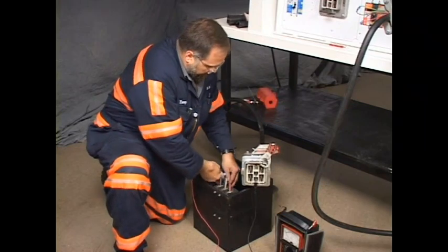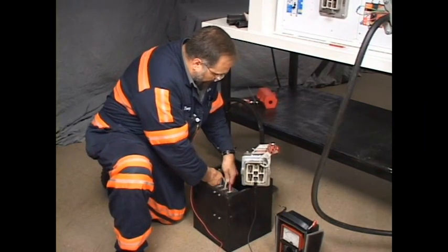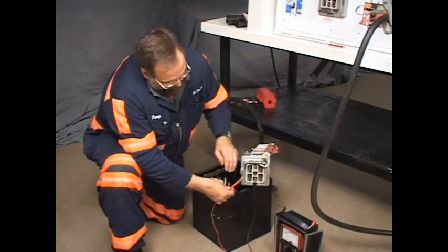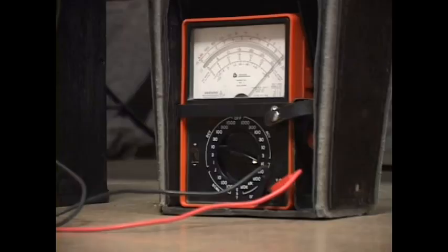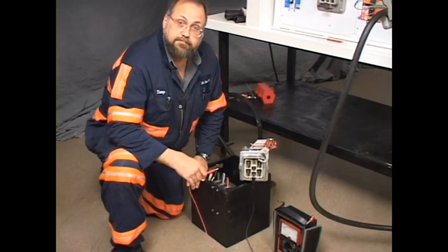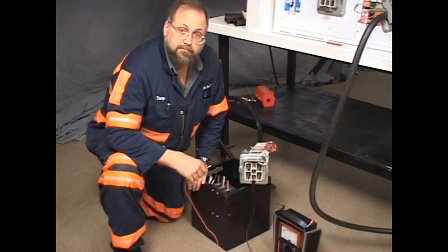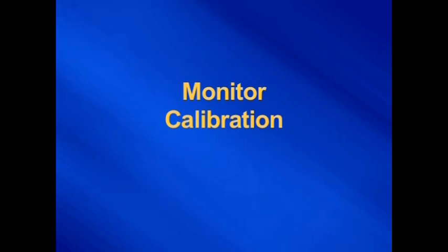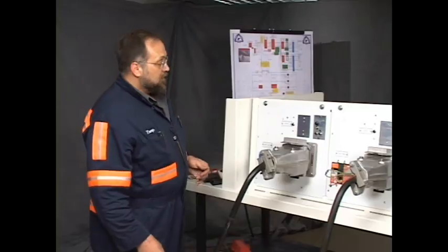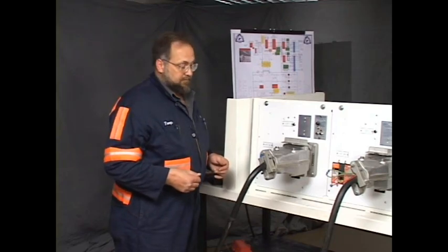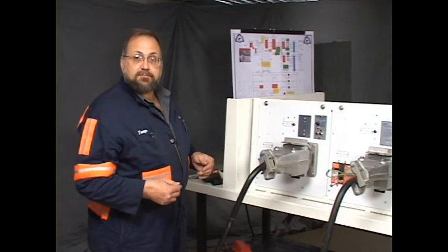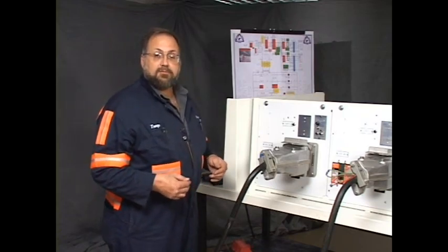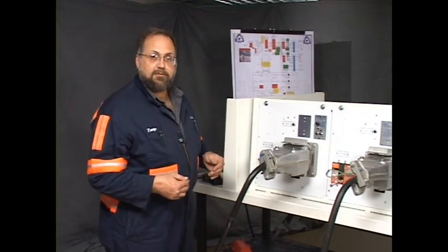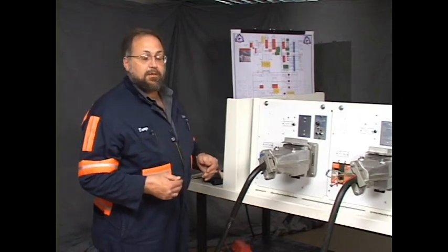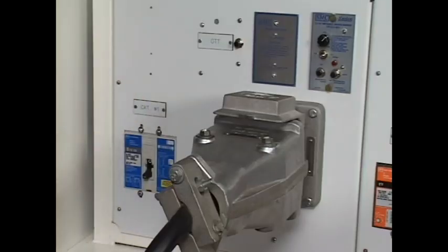I'm going to connect this monitor wire back up to show you what it should read. From the monitor pin to the ground blade, it should read a full circuit, full scale continuity with low resistance. There you have it. Should the grounding conductor begin to fail and its resistance changes as it fails, as it becomes less competent, it will give you a different reading, ohmic value. If that reading should increase 3 ohms, the monitor should detect that and open the circuit breaker.